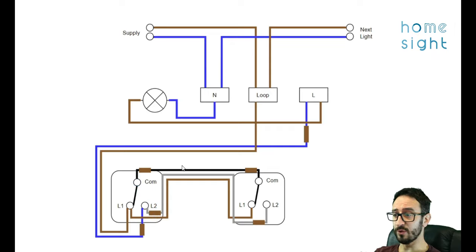We'll have a common which you will use to link using UK standard wiring a black wire but again it's live or it could be live so we put this brown sleeve on it as well so that's linking the two commons together, and from the L1 we're linking that to the next L1 with our brown wire and our L2 with our grey wire to our other L2. Now let's just talk through that. How does that work?